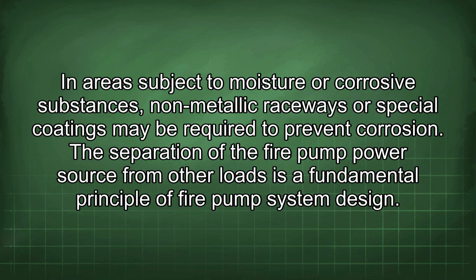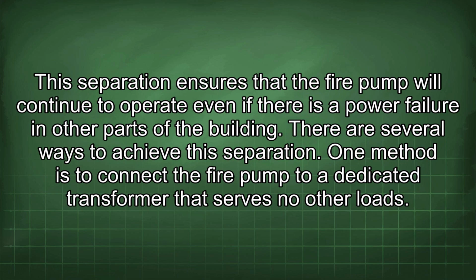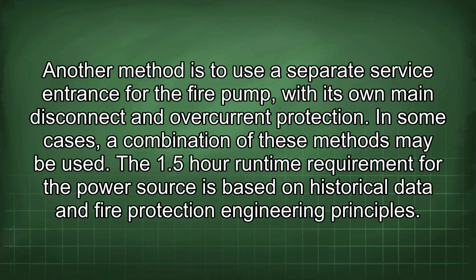The separation of the fire pump power source from other loads is a fundamental principle of fire pump system design. This separation ensures that the fire pump will continue to operate even if there is a power failure in other parts of the building. There are several ways to achieve this separation. One method is to connect the fire pump to a dedicated transformer that serves no other loads. Another method is to use a separate service entrance for the fire pump with its own main disconnect and overcurrent protection. In some cases, a combination of these methods may be used.